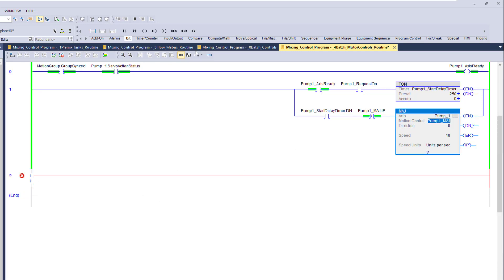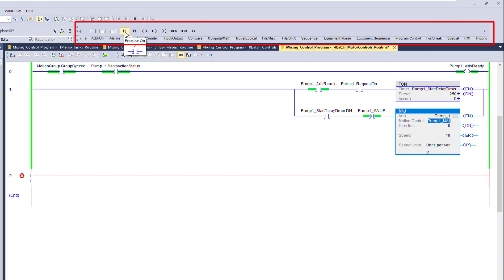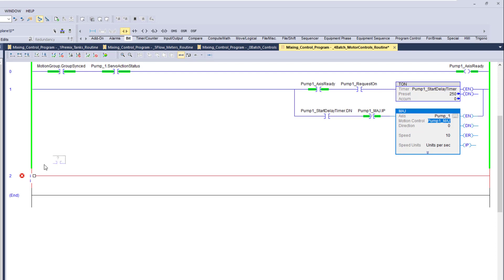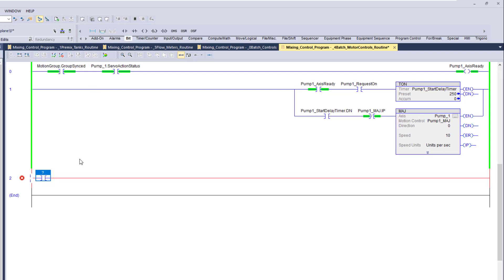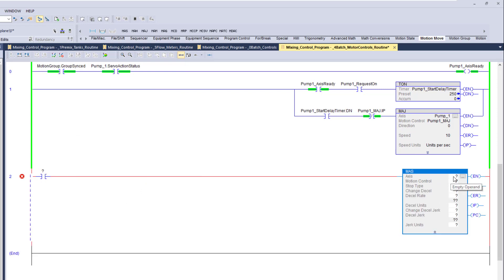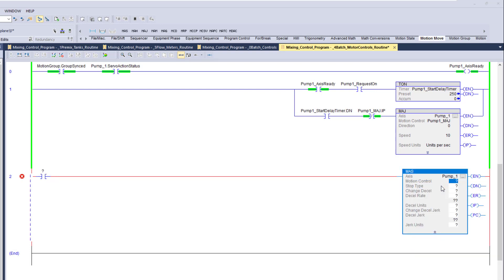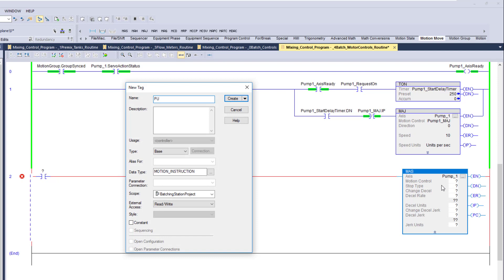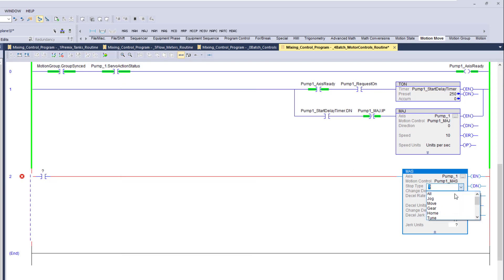We'll add one more rung to control the stop. We'll grab an examine on contact, then go to motion move and select motion stop. This is our motion stop — it will pick Pump_1 as our axis. The motion control tag we'll call 'pump one MAS' — motion axis stop.